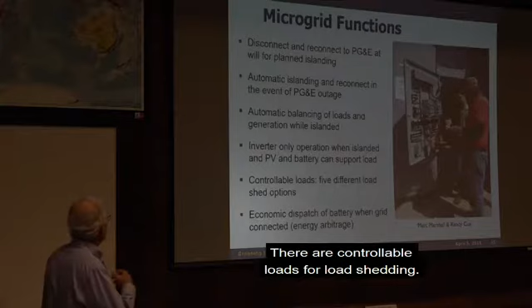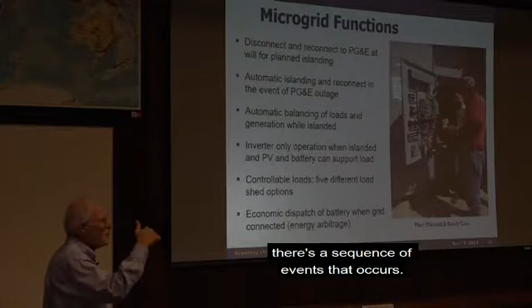There are controllable loads for load shedding. So in an event, if we need to disconnect certain loads, there's a sequence of events that occurs. First, we can turn off the tribal office, then in a rotating fashion turn off some of the HVAC, and then some of the ventilation, eventually getting down to the point where the only loads are the life and safety loads.